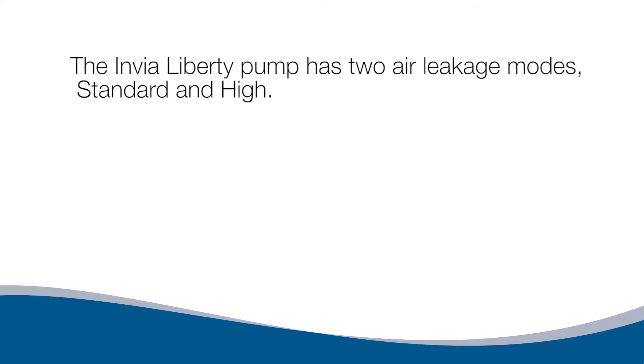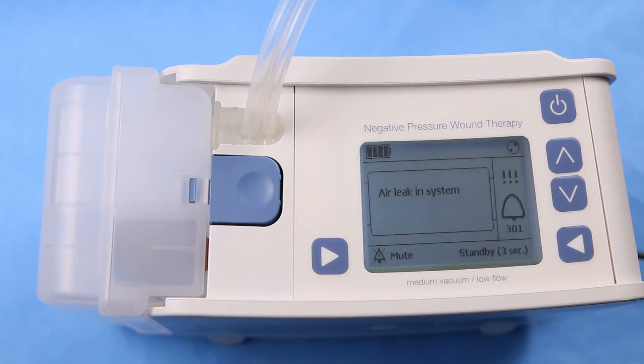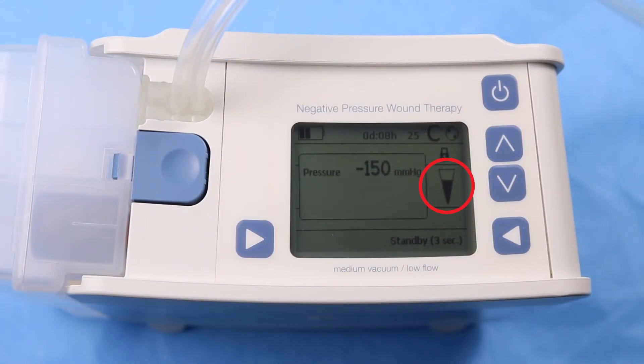The Invia Liberty pump has two air leakage modes: Standard and High. In the Standard setting, when the pump is first turned on, an audible alarm will sound within two minutes if the set pressure is not maintained. For larger wounds, use the High air leakage setting. Follow the alarm chapter in the instructions for use, Air Leak in System, Alarm Code 301. When the indicator is half full, it is recommended to check all connections on the pump side and ensure the dressing is sealed tightly. The air leak indicator alarm will not sound in this situation.